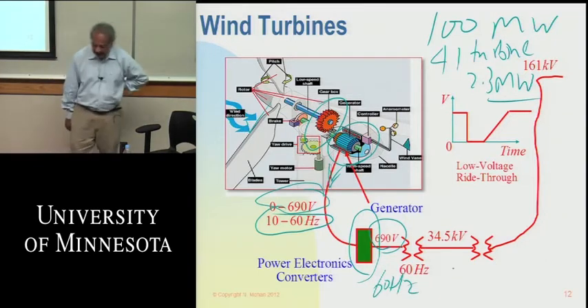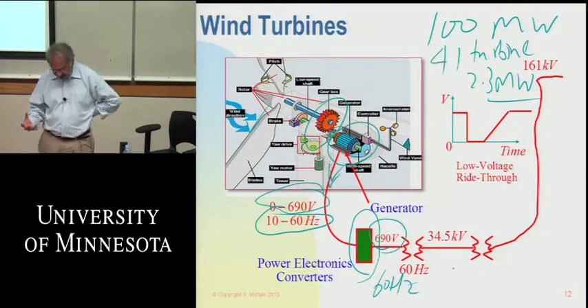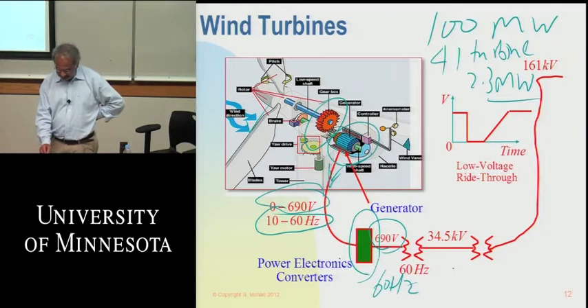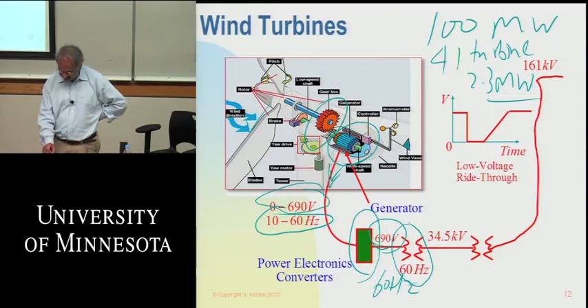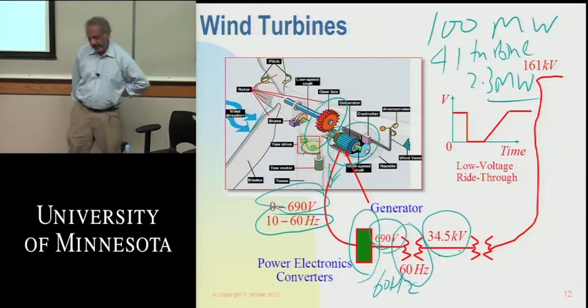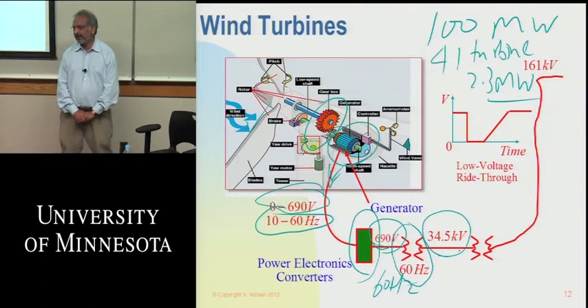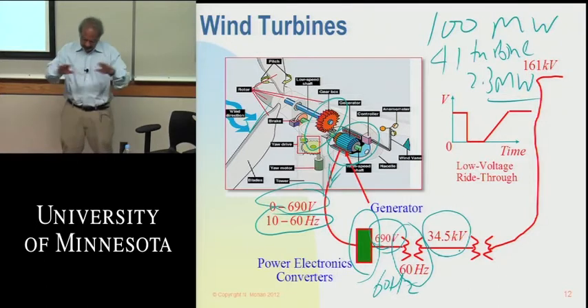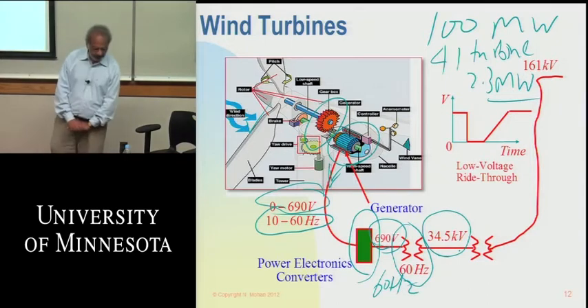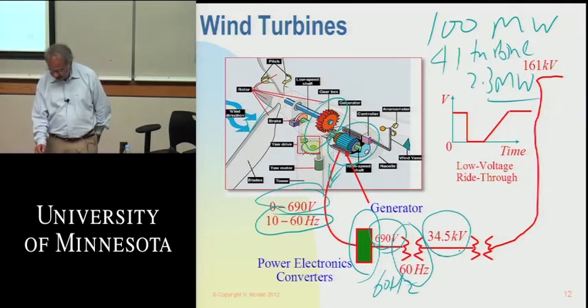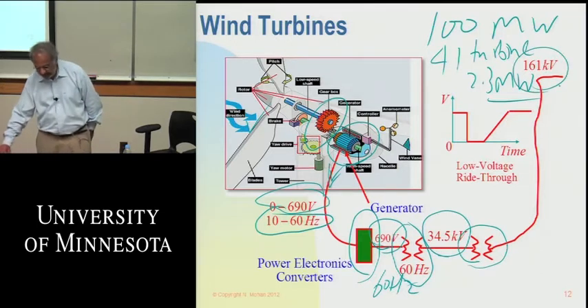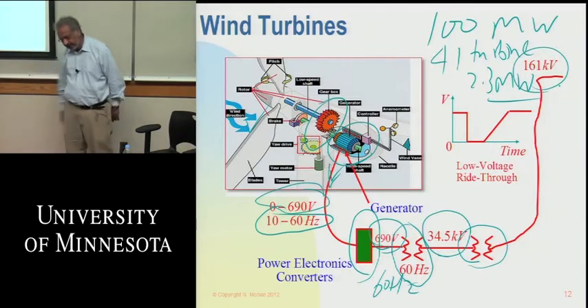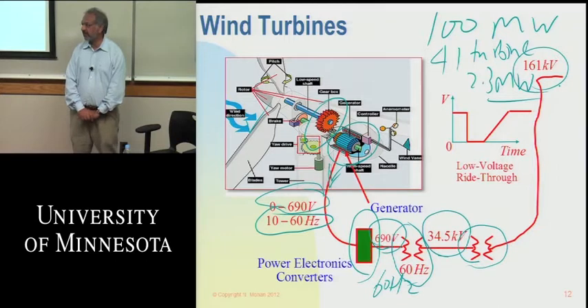At the base of each tower there's also a fairly large 60 hertz transformer, which transforms this low 690 volts to 34.5 kV. That was the collection voltage, and all 41 wind turbines were connected to this 34.5 kV network. Then there was a transformer which transformed 34.5 kV to 161 kV, and that power was carried on transmission lines to the Xcel Energy system.